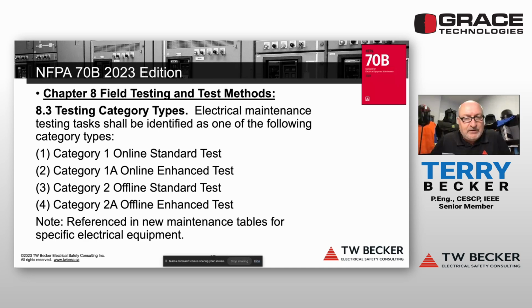This is where we get into some of the new content in the core chapters - field testing and test methods. There are now 4 categories of electrical maintenance testing: category 1, online standard test; category 1A, online enhanced test; category 2, offline standard test; and category 2A, offline enhanced test. These testing category types are defined in new tables I'll show you shortly, within the chapters for specific electrical equipment maintenance, defining the test and categorizing it within the applicable table.